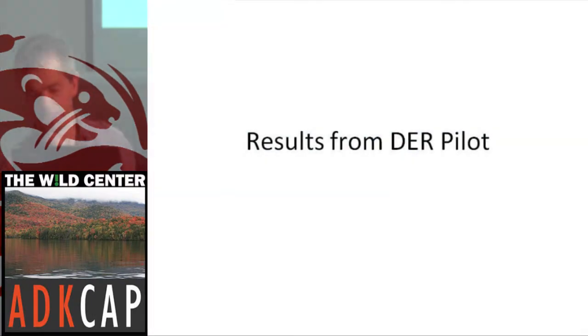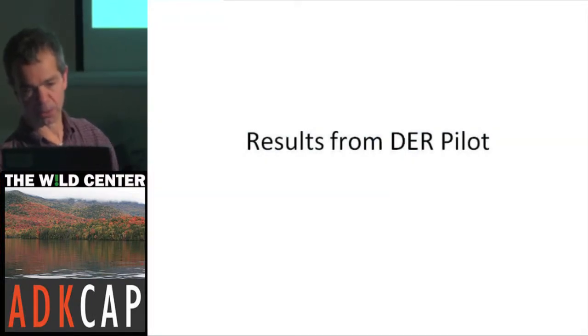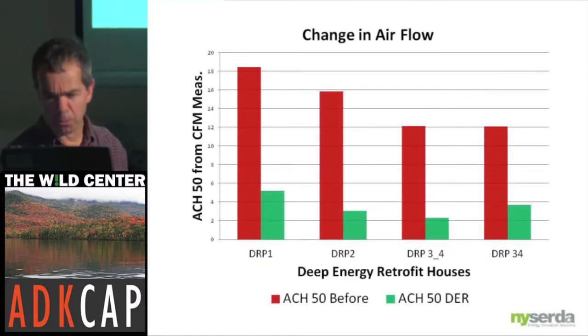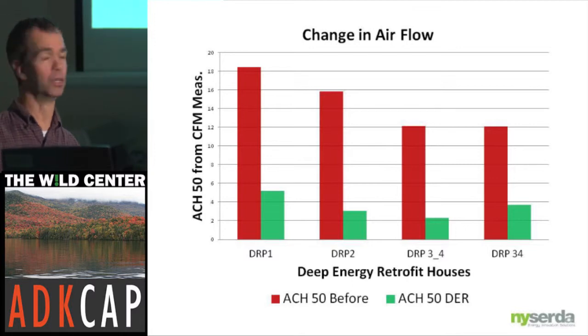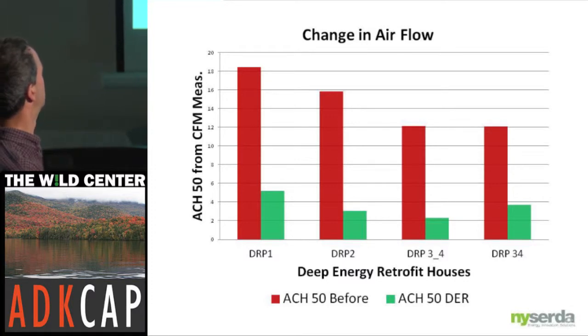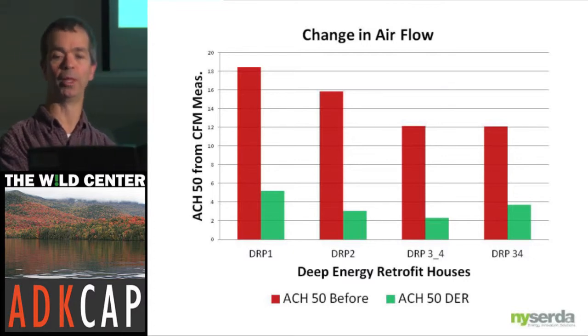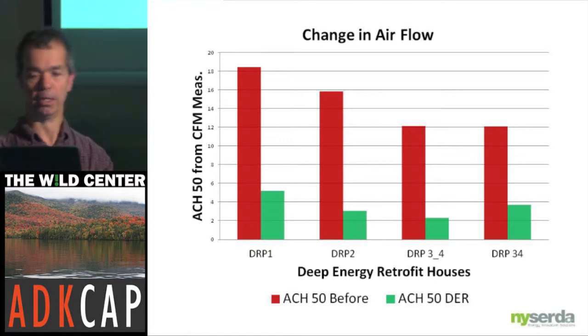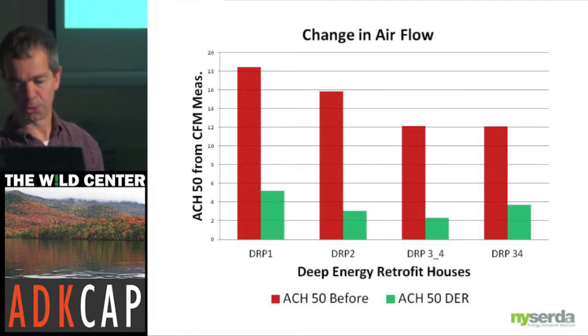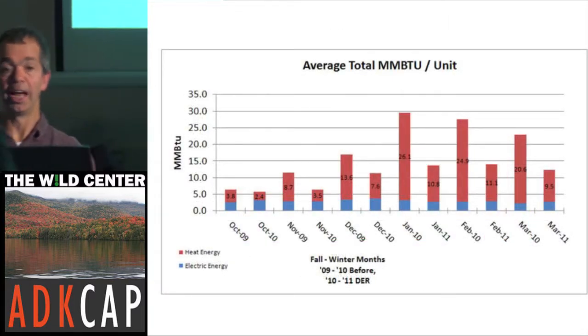These are the results — the data. I was going for a 70% reduction with certain target values on the loads. This is what we did with the airflow levels of the four houses. We took our best from 18.5 ACH50 down to 4.8, so we definitely tightened the houses. That's the combination of the thermal ply, the rigid taping, the joints, the window box air sealing.